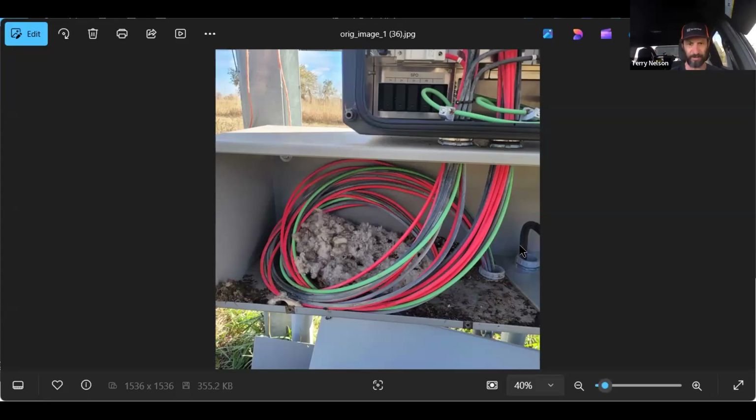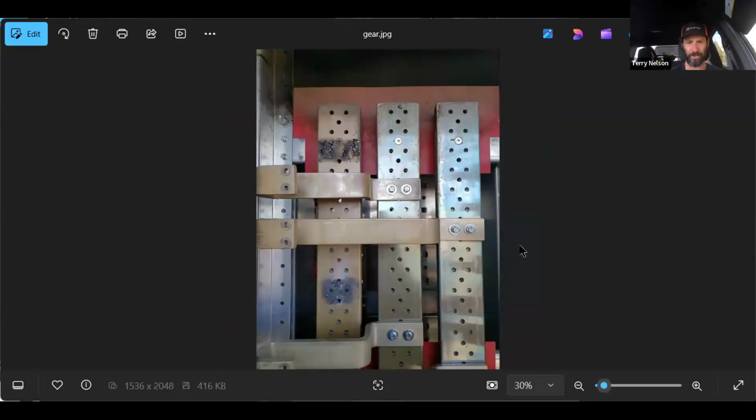Let's see if I've got anything else. Some more heat damage. I think the biggest thing is heat is a recurring issue in solar farms, especially these larger utility scale sites where we're running 2 or 3 to 5 to 10 megawatts. These sites have a lot of power running through them, so maintaining them with a thermal imaging camera to be able to see these heat problems is crucial. It looks like my internet is unstable, so that's all I've got.